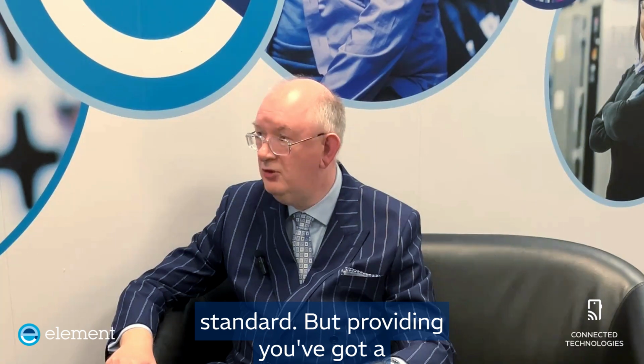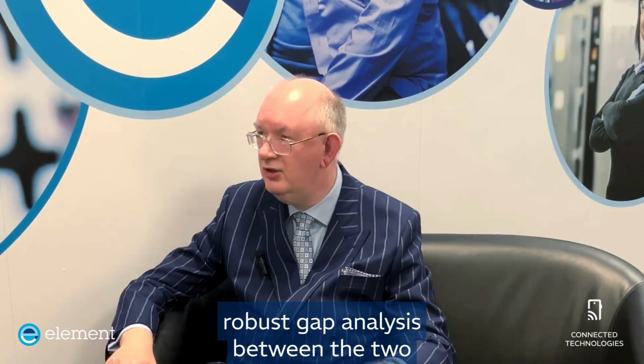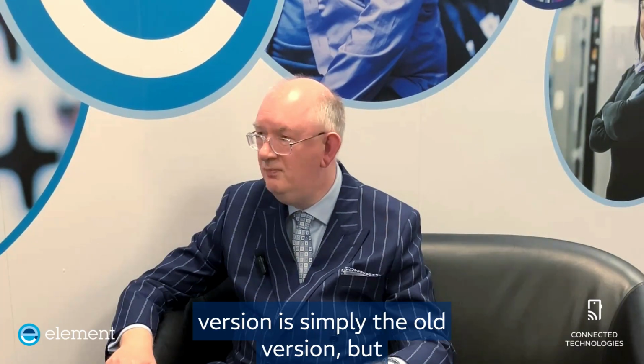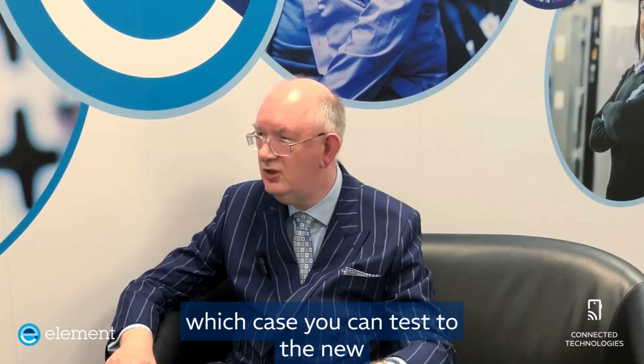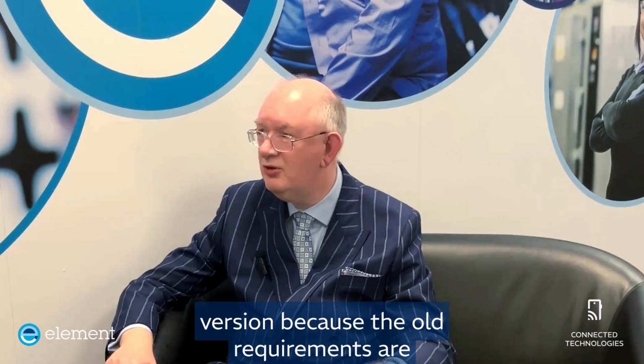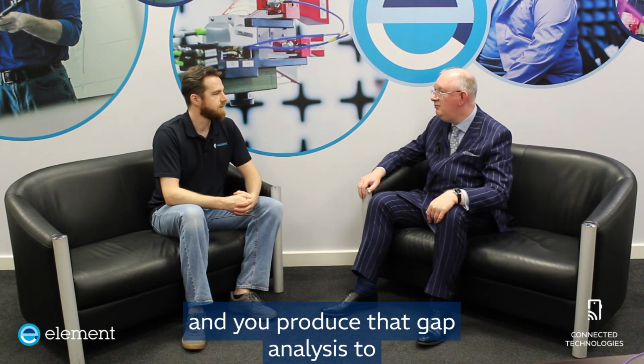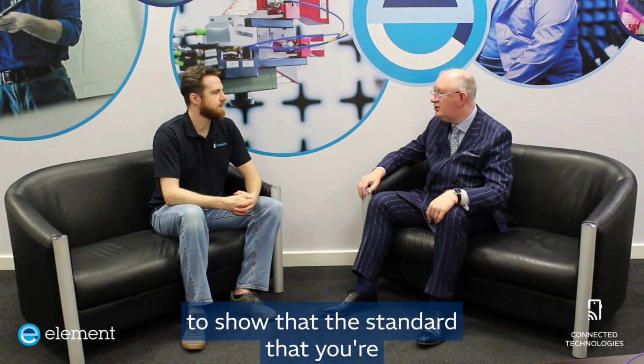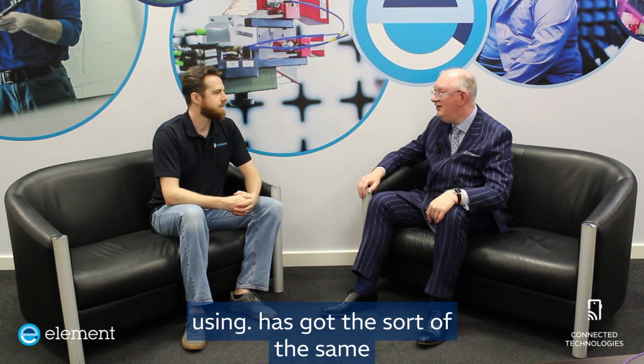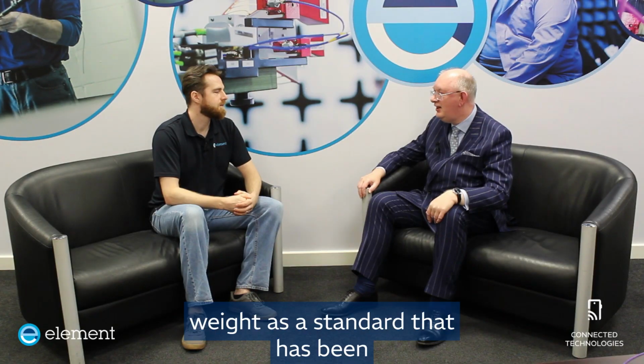Obviously, the watertight case is to test to the harmonised standard, and then to test to the new standard. But providing you've got a robust gap analysis between the two versions, you may find that the new version is simply the old version, but there's some additional requirements, in which case you can test to the new version because the old requirements are identical to what was in the version that's in the official journal. You test to the newer version, and you produce that gap analysis to support it. The extra work is that you've just got to do the hard yards to show that the standard that you're using has got the same weight as a standard that is published in the official journal and is harmonised.